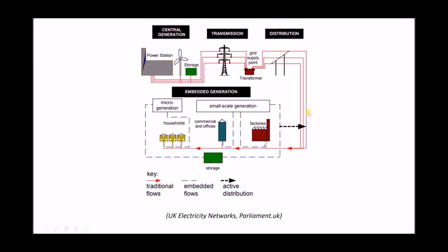Take the southwest of England as an example — we know they have an energy deficit, so any electricity they produce will be used locally and certainly doesn't need to be transmitted northwards. Alongside micro generation we have small-scale generation, such as a small onshore wind farm or a solar array, used to supply local factories and commercial offices. Any surplus is fed into the distribution network through active distribution — it is not fed into the transmission network.